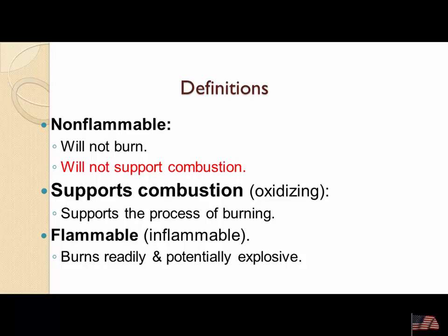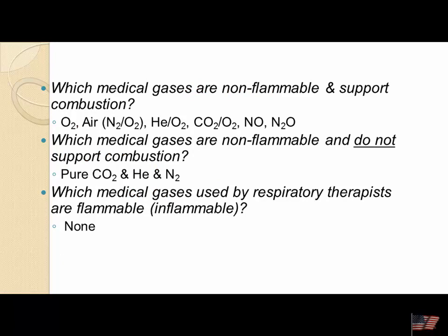But that means that it burns readily and it's potentially explosive. Again, we will not encounter any gases that are flammable in nature. So the ones that are non-flammable and support combustion are anything that has oxygen as a component of it. So things like oxygen, things like air, which contains nitrogen and oxygen, heliox, helium and oxygen combined, carbogen, a combination of carbon dioxide and oxygen is a mixture.